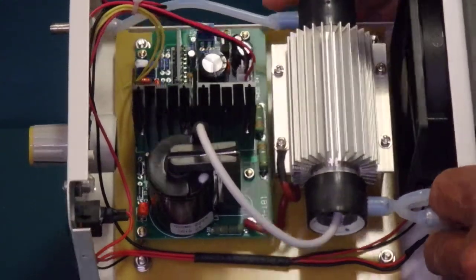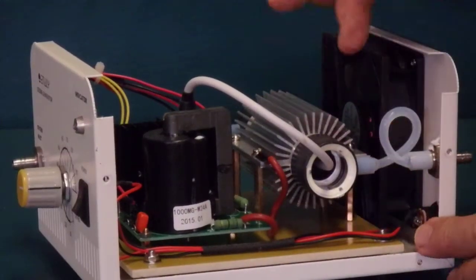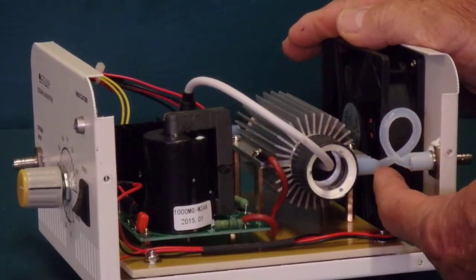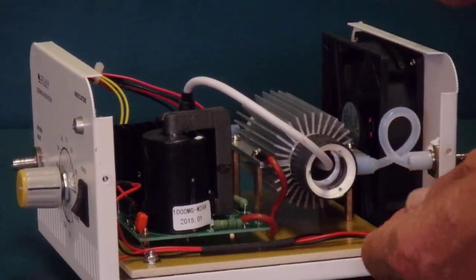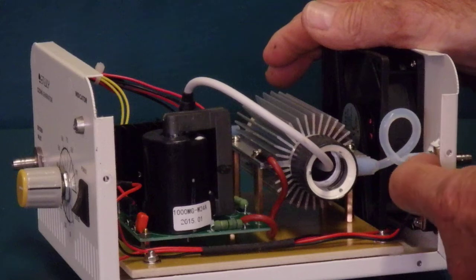We replace both sides, the oxygen in and the ozone out. Notice the loop here. The loop is simply to relieve the stress of the other existing tubing. These are offset and so they induce a natural stress point in the tubing between the generator and the outlet.